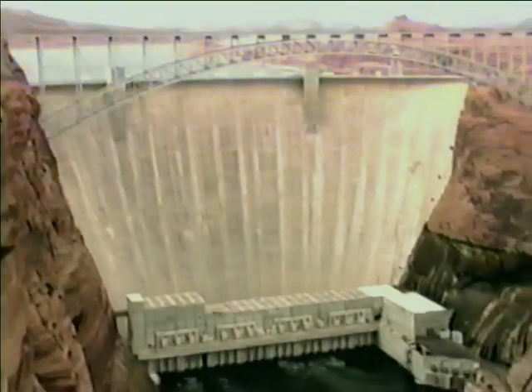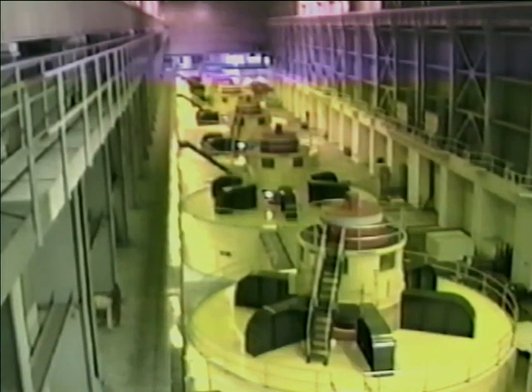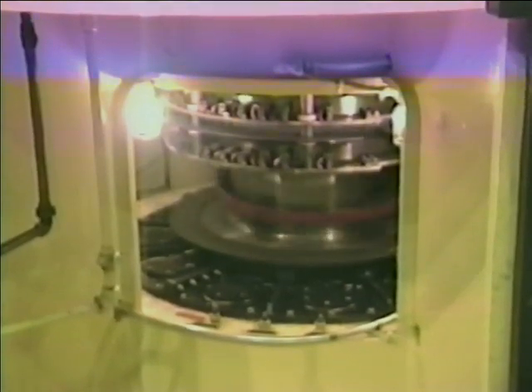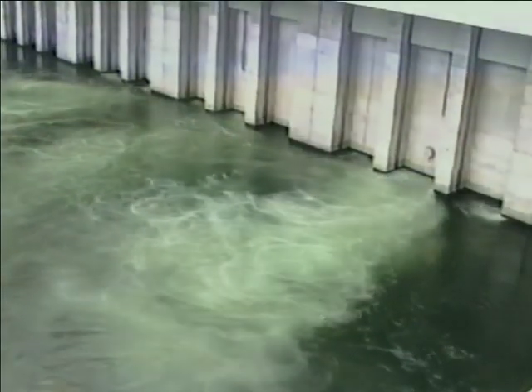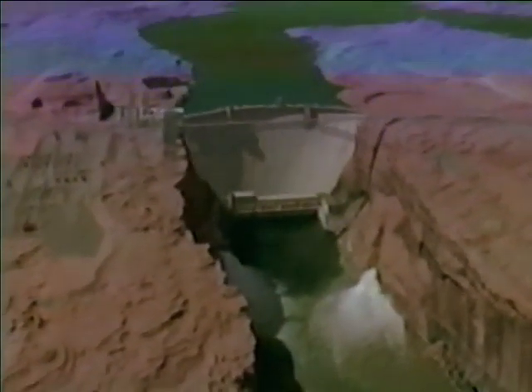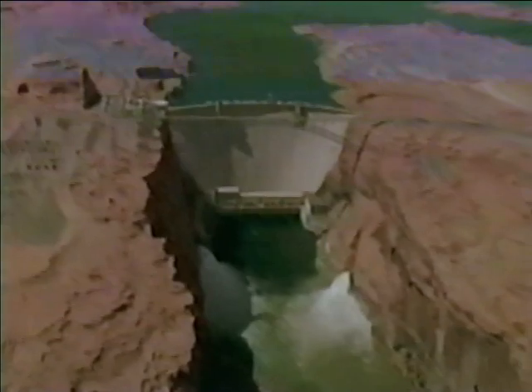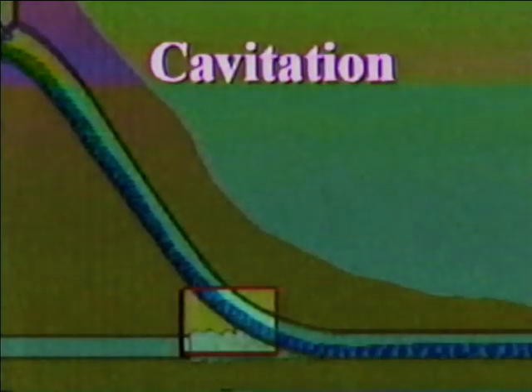And so the 1960s and the 1970s passed. Glen Canyon Dam and Power Plant operated generally as planned. Lake Powell filled in 1980, and practically everyone assumed it was an extremely rare event, unlikely to happen again for several decades. The spillway was tested and was found to have been slightly eroded by cavitation. It was understood that use of the spillway was certain to cause cavitation damage.